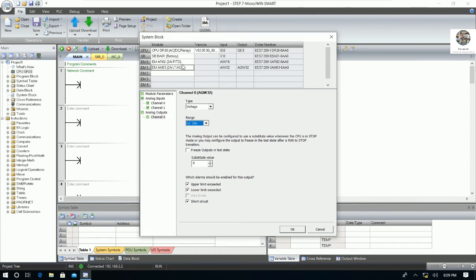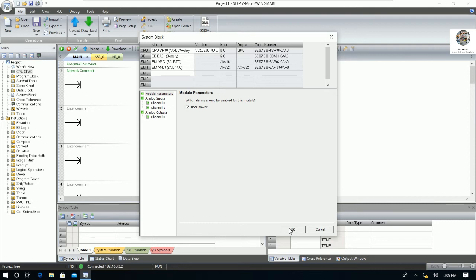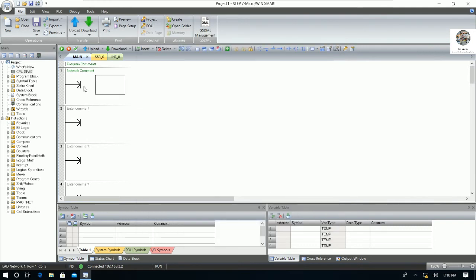Click OK after the hardware configuration is done. Here are the addresses we will use: the first module uses AIW16 to AIW18 for the two RTD input channels. The second module starts from AIW32 for the three input channels, and AQW32 for the analog output. The addresses are arranged automatically — we don't need to set them manually. Click OK.